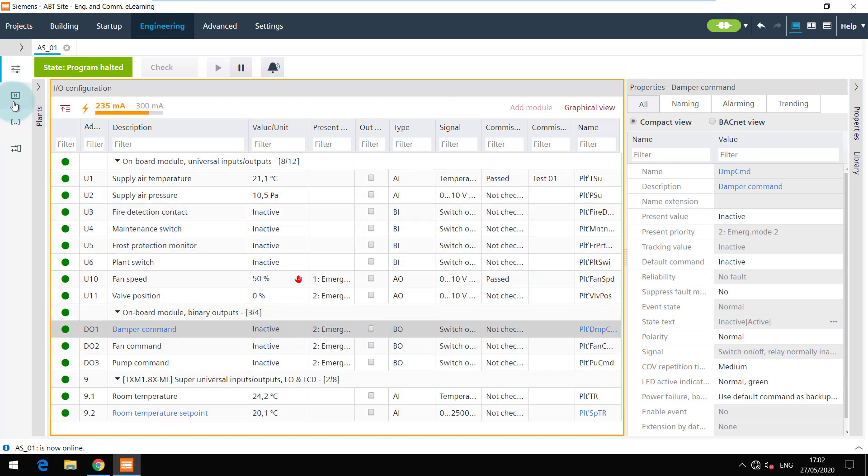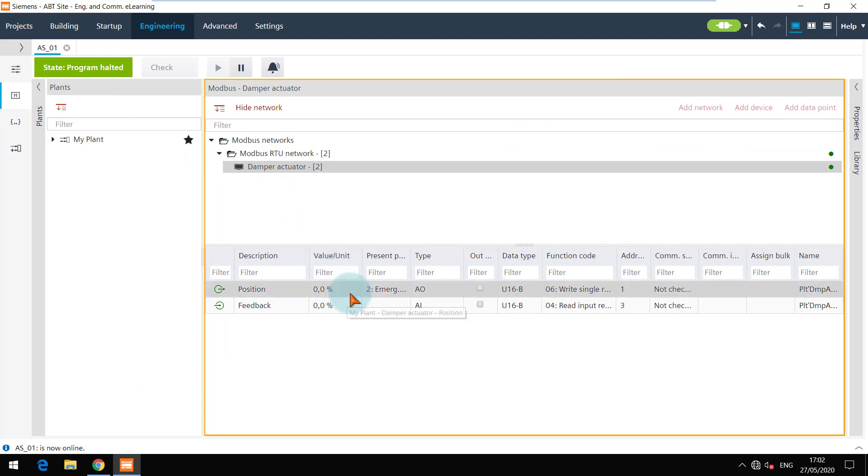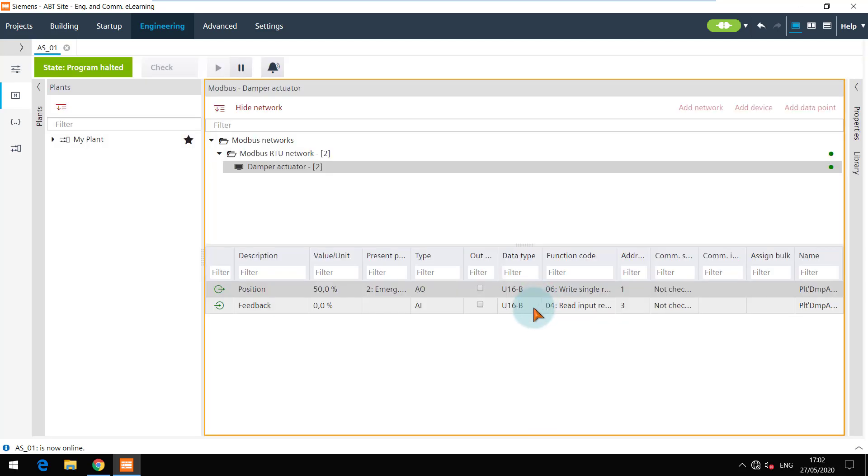Let's now also check the Modbus device. I will change the setpoint of the damper to 50 percent and you can observe that the feedback changes. It also reaches a value of 50.